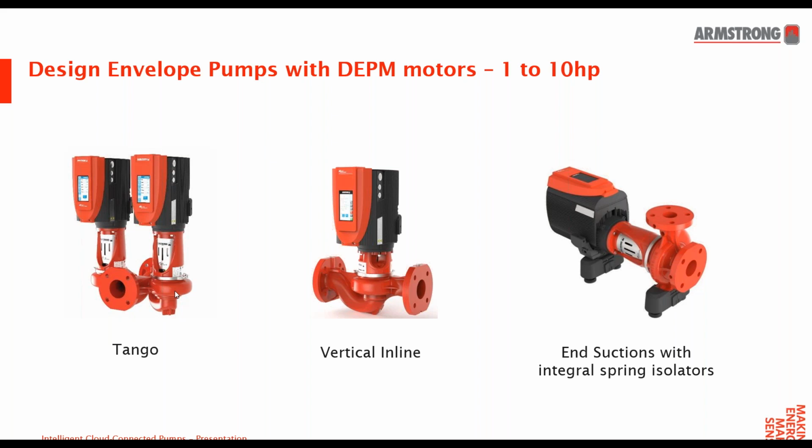For example, the minimum head or the zero flow head, a lot of people do change that on site, and they lower that to get more energy savings, because they find that they're still satisfying all of the loads, and they lower that to a lower value, and they're able to save more energy. And then if, for example, the pump is overestimated and you get less system resistance in the field, you want to change your design point. You want to lower your head to the actual on-site head. You could also lower that in the field. So you change the parameters, but you don't need to reprogram the map. The map would stay the same.